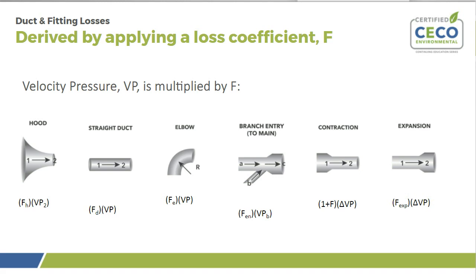A contraction or reducer is, because Q is going to be the same, the area of the duct shrinks, so velocity has to increase. So by increasing the velocity, we're going to encounter a loss there, which is dependent upon the velocity delta between 1 and 2. An expansion, you see on the far right, you actually have a regain because the airstream is slowing down. However, that regain is not usually as high as what it is for a contraction.